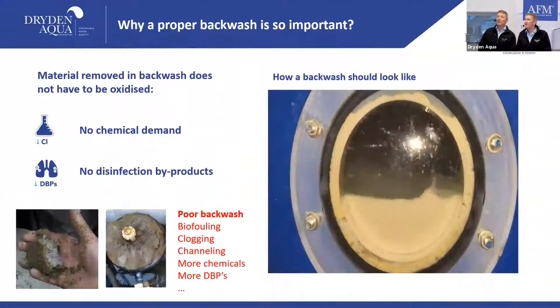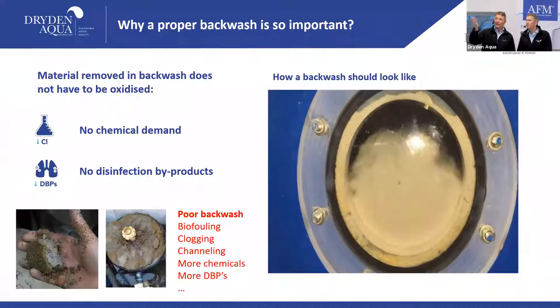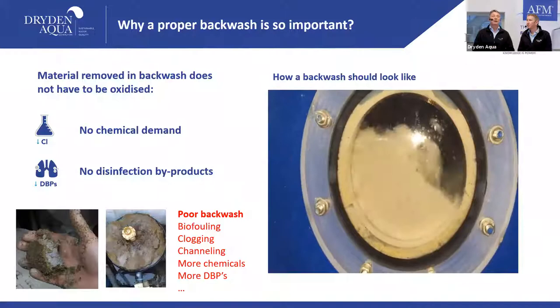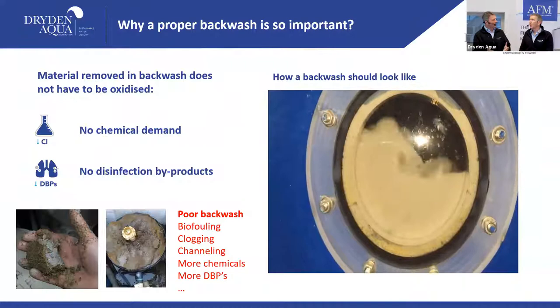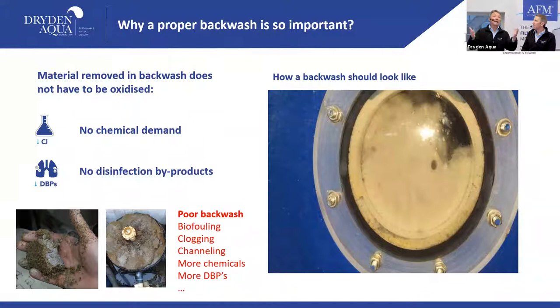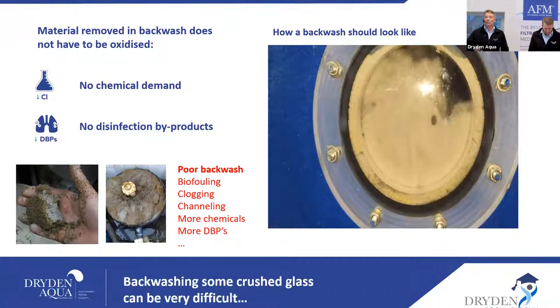A sight glass is essential, especially in commercial filters, so you can see how the backwash looks. Whatever is not properly backwashed stays in the system, creates chlorine demand, produces disinfection byproducts, and leads to clogging and biofouling. Think of it like a bin that must be emptied regularly.